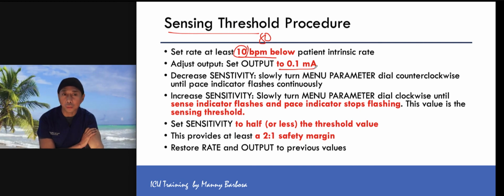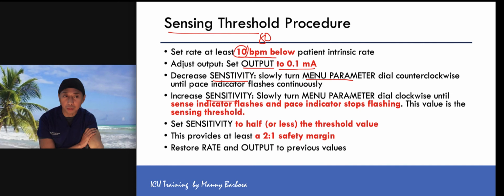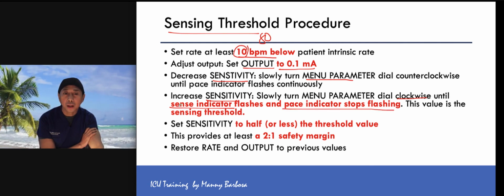And then you go slow. You set your output to 0.1 because you gotta start low and then go up. And decrease your sensitivity by turning the menu parameter. Okay, so when you increase the sensitivity, you are slowly turning the menu parameter clockwise until the sense indicator flashes. This is the blue light. So the pace indicator stopped flashing. So when it's sensing, the blue, you should not be seeing the green light, because the blue light is sensing, saying, oh, I saw your own rhythm, so I'm not going to pace, okay? And when you do that, that is your sensing threshold.